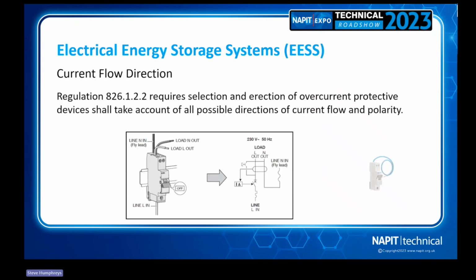One slide we always like to show on this, because this is quite big in the industry at the minute, is when we're fitting these kind of systems, and this applies to anything that feeds back in, so solar PV would fall into this remit. If we're using overcurrent protective devices, whatever that may be, we need to take account of possible directions of current flow and its polarity. So you can see there on the diagram, the example where we've clearly got marked line in and line out on our load. These are classed as unidirectional devices because they're clearly marked for that.